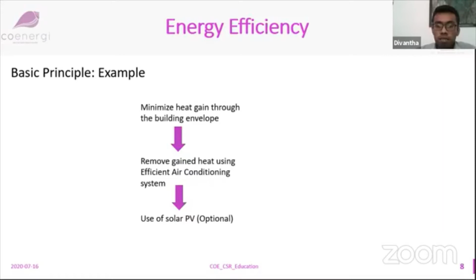When you design a building from scratch, the first design consideration is to orient the building properly to minimize solar heat gain, and also to determine the basic shape of the building and other parameters such as shading to minimize solar heat gain further. This is usually done using energy simulation during the early, schematic design phase of the building.